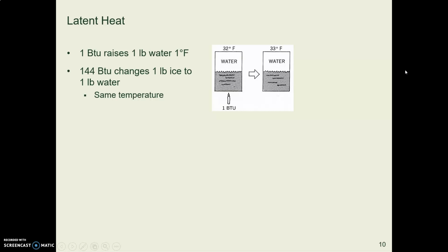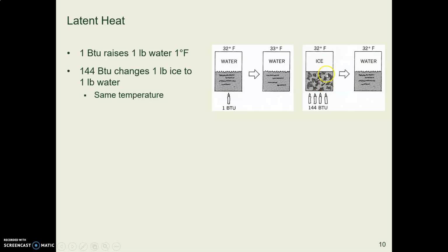There's actually a surprising amount of energy involved in latent heat. So for example, to raise a pound of water 1 degree Fahrenheit takes 1 BTU of energy. To change 1 pound of ice to 1 pound of water without changing the temperature takes 144 BTUs. That's latent heat.